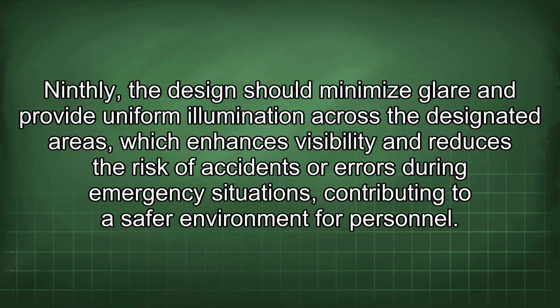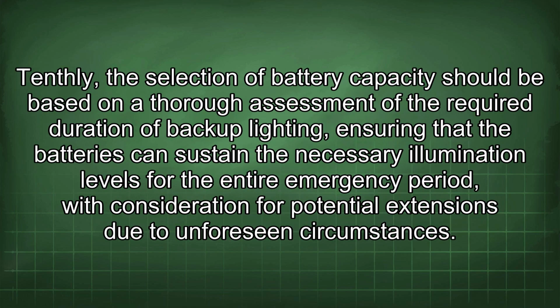Ninthly, the design should minimize glare and provide uniform illumination across the designated areas, which enhances visibility and reduces the risk of accidents or errors during emergency situations, contributing to a safer environment for personnel. Tenthly, the selection of battery capacity should be based on a thorough assessment of the required duration of backup lighting, ensuring that the batteries can sustain the necessary illumination levels for the entire emergency period, with consideration for potential extensions due to unforeseen circumstances.